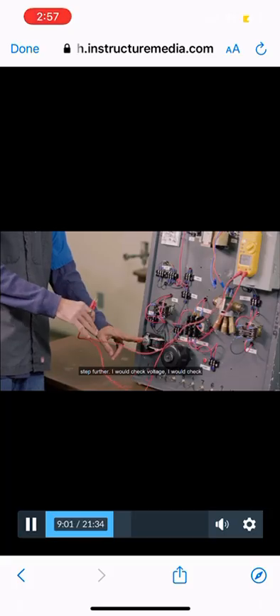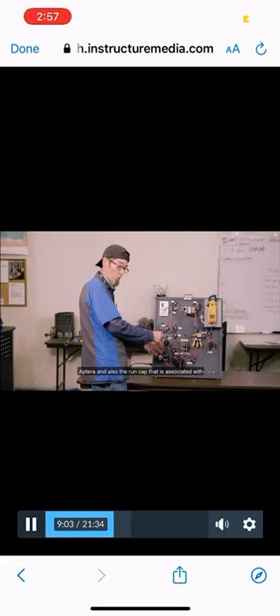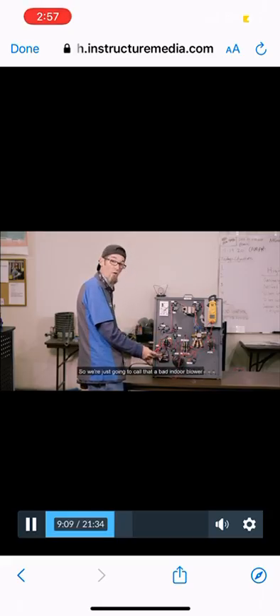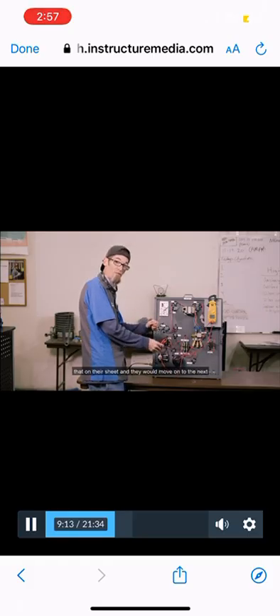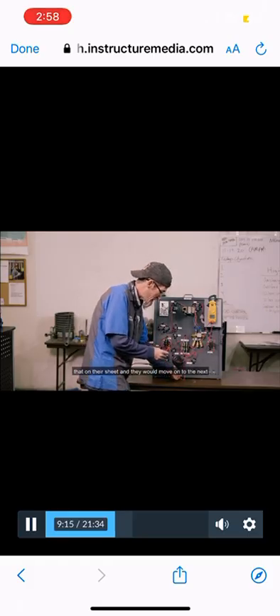Now in the field, I would take this a step further. I would check voltage, I would check amp draw, and also the run cap that is associated with this. But because we're working on a limited space board, we don't have any of that, so we're just going to call that a bad indoor blower motor. Once the student completes that, they would log that on their sheet, and they would move on to the next one.